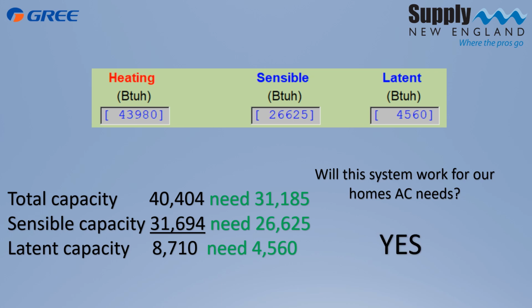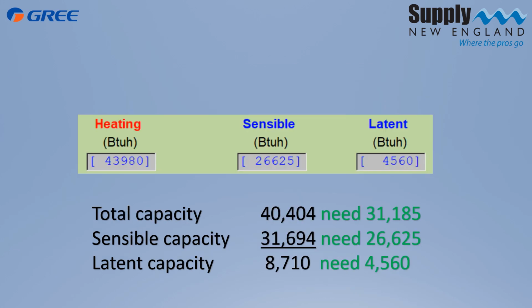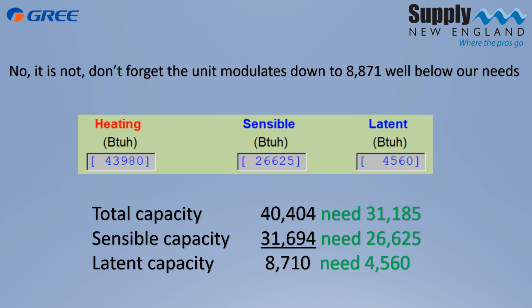Yep, it works. But right about now, you guys are saying, Nancy, you told me not to oversize. Oversize is bad, right? It is. Thing to remember though, guys, modulation. This unit will modulate all the way down to 8,871 cooling BTUs. So does it work for our system? It works, and it works really well because we're going to be on lower modulation most of the time, and that's where we really experience our energy savings.